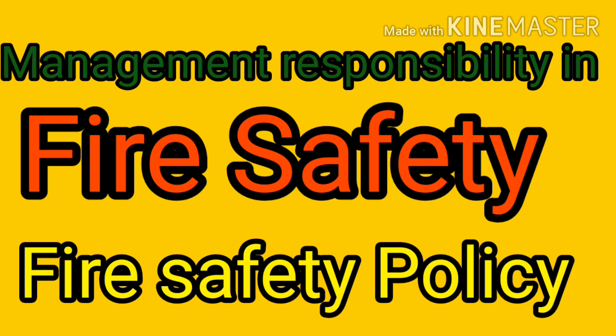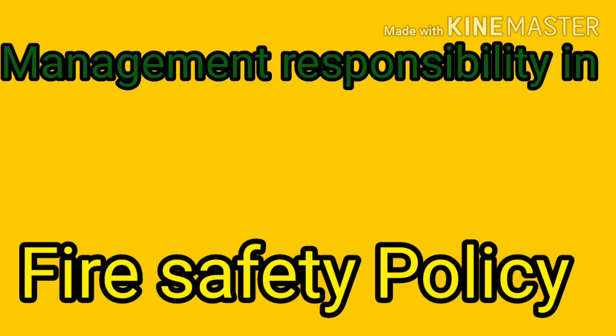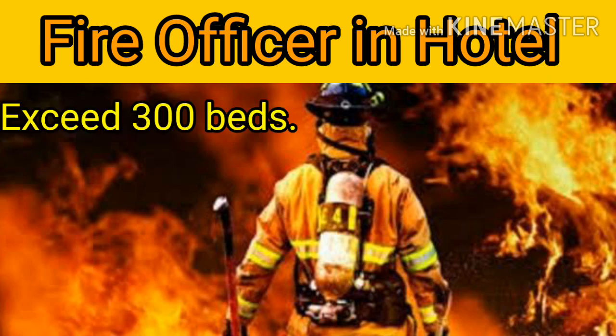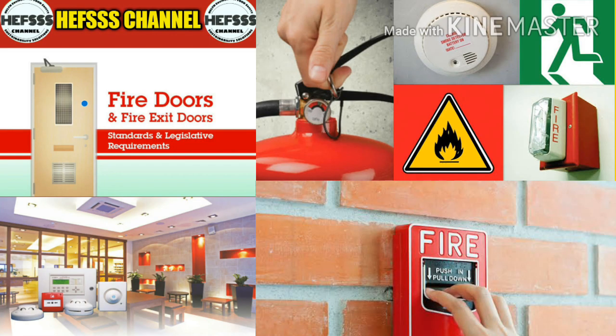For high or low rise hotels, if the number of sleeping accommodations exceeds 300, a qualified fire officer shall be appointed. He shall report directly to the chief executive. A fire control room shall be established on the ground floor near the main entrance in accordance with Indian Standard 2189 of 1988. All employees should be trained to raise an alarm in case of fire and to use first aid or firefighting equipment. Okay, it's very important. An alarm system is mandatory, that is called the manual call point or fire alarm system.